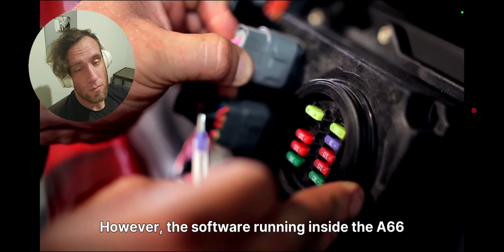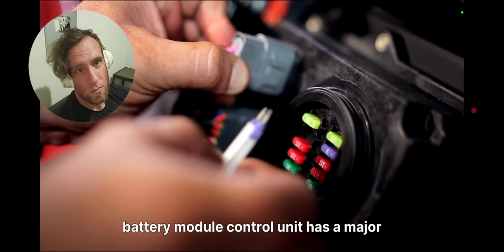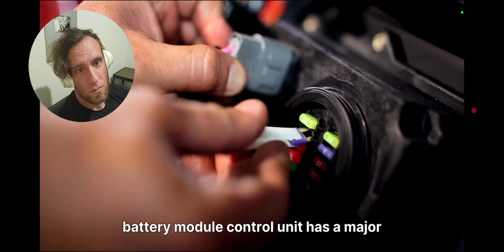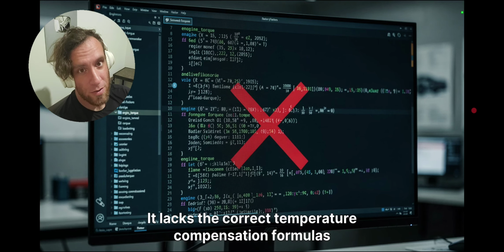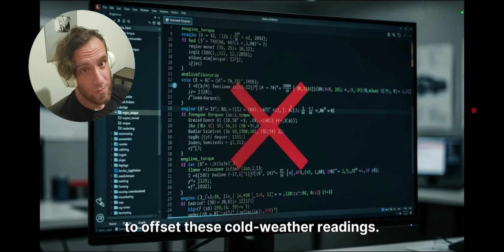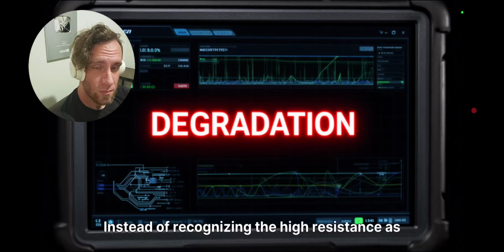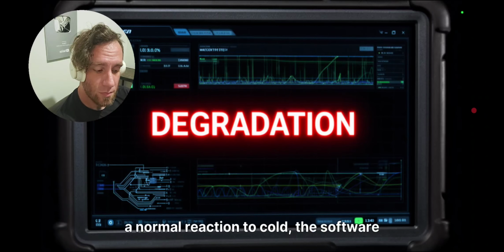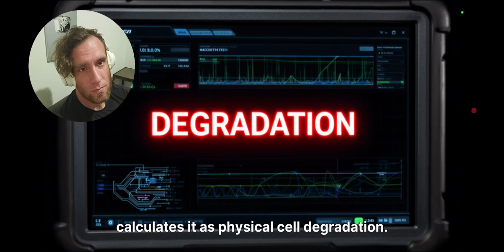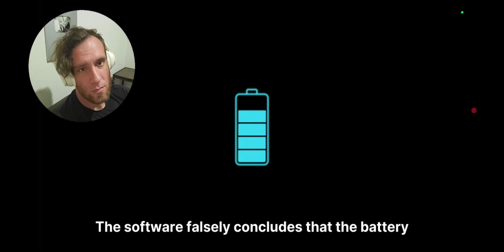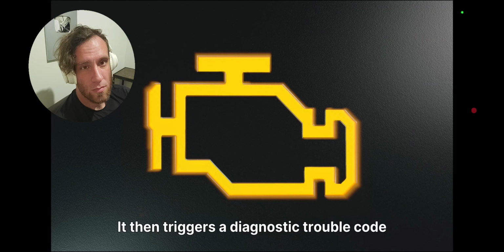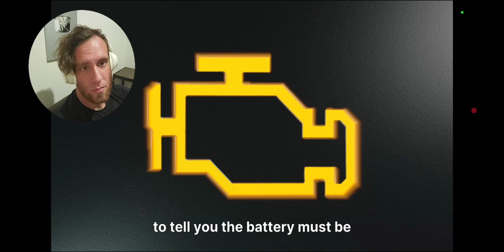However, the software running inside the A66 battery module control unit has a major design flaw. It lacks the correct temperature compensation formulas to offset these cold weather readings. Instead of recognizing the high resistance as a normal reaction to cold, the software calculates it as physical cell degradation. It falsely concludes that the battery has reached the end of its physical lifespan, then triggers a diagnostic trouble code telling you the battery must be replaced.